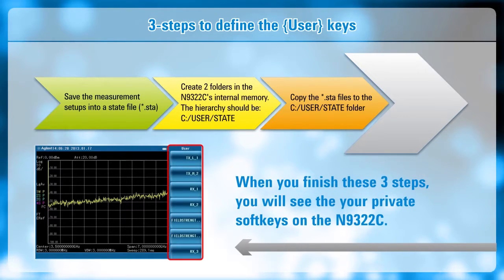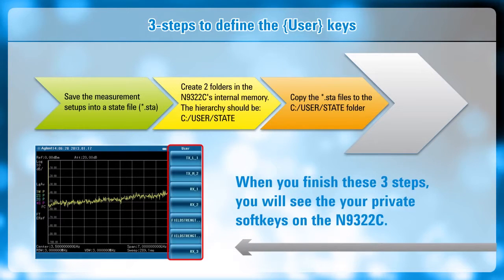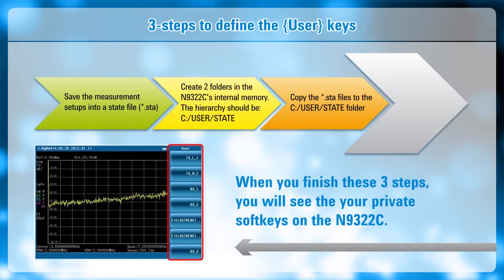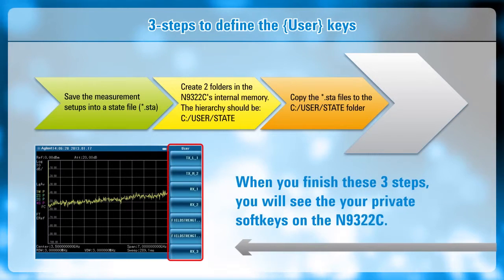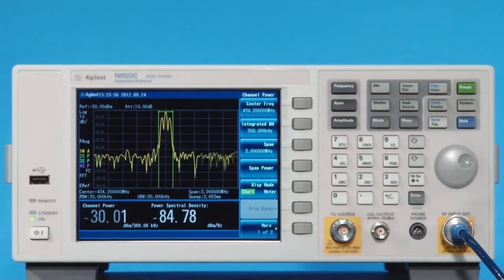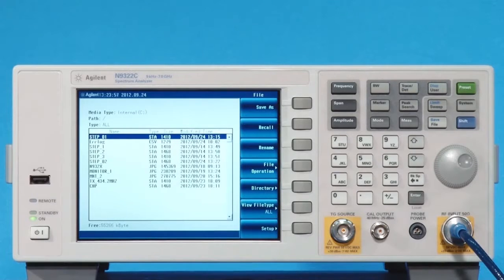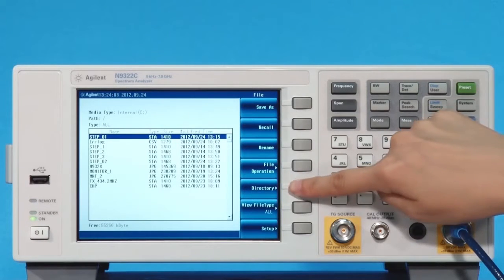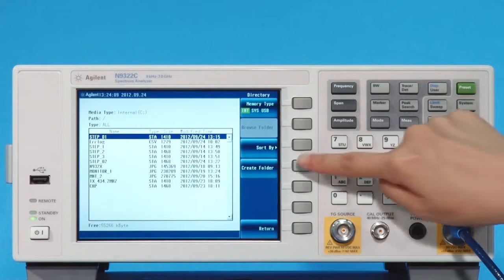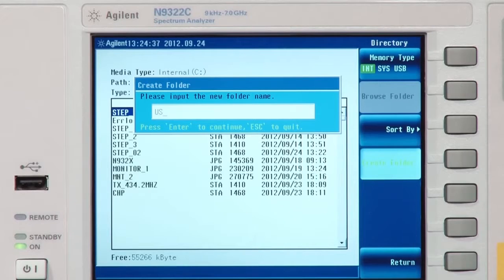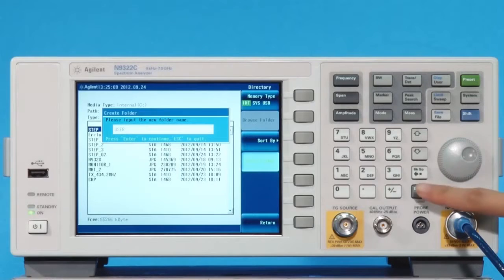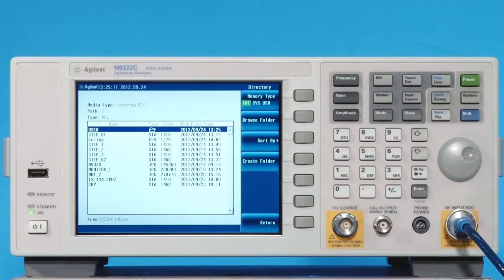Let me show you how easy it is with an example. For this demonstration, we'll assume that you've already saved a couple of state files in the analyzer's internal memory. To begin, press the File hard key and enter the File Management screen. Press Directory and Create Folder soft keys. Using the numeric keypad, name the folder User.